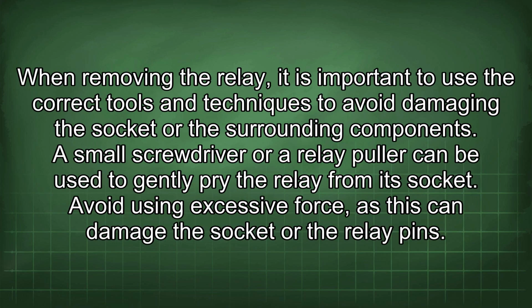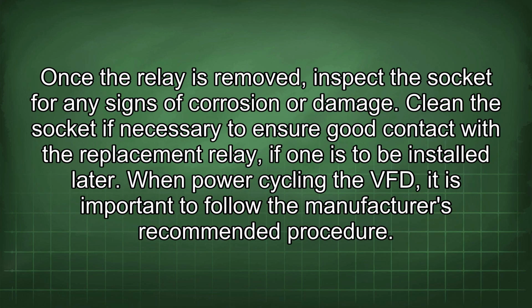When removing the relay, it is important to use the correct tools and techniques to avoid damaging the socket or the surrounding components. A small screwdriver or a relay puller can be used to gently pry the relay from its socket. Avoid using excessive force, as this can damage the socket or the relay pins. Once the relay is removed, inspect the socket for any signs of corrosion or damage. Clean the socket if necessary to ensure good contact with the replacement relay if one is to be installed later.